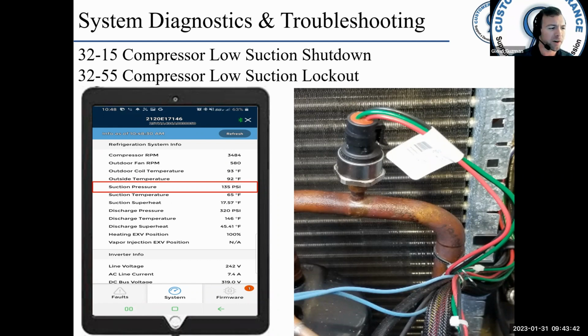Okay, but there are soft and hard low pressure limits in code 3215. The low pressure limit can be exceeded up to 2 minutes before the code is generated, while exceeding the hard limit results in an immediate 3215. The low pressure limits are compressor and RPM dependent, but typically 30 psi and 15 psi are what you're going to see. 4 occurrences of 3215 in a 2-hour period will give you a 2-hour lockout.